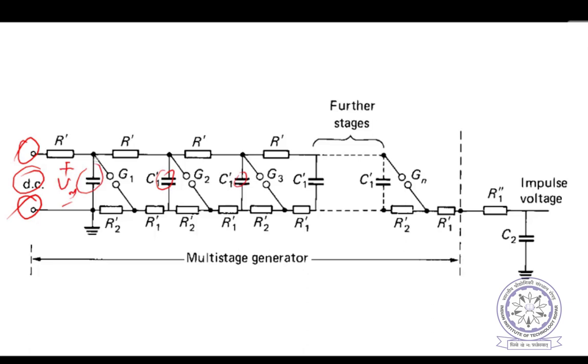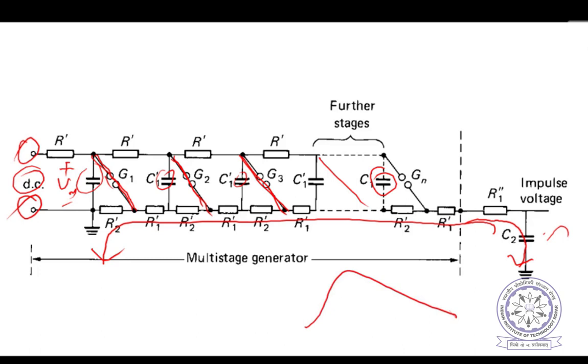The moment you trigger these sphere gaps, what will happen? Earlier they were in parallel, charged in parallel to plus minus Vm. But the moment you trigger these gaps, these capacitors will get connected in series. So high voltage will be generated. That voltage, from these capacitors during their discharging period, will charge this C2. After C2 reaches its peak, C2 gets discharged through this path. This is how a double exponential wave is obtained using this Marx circuit.